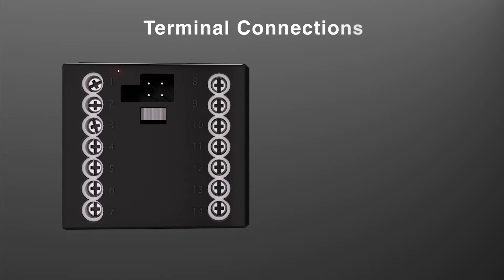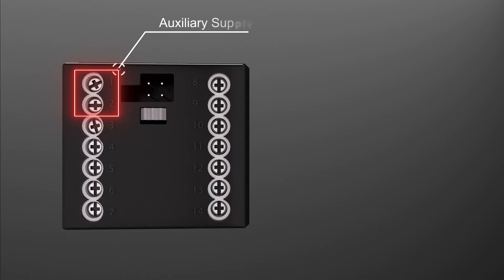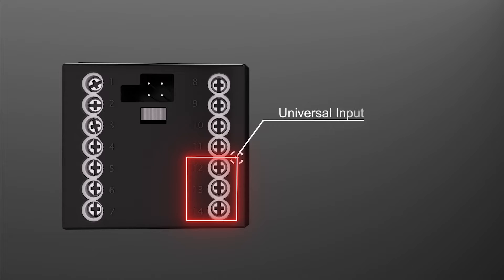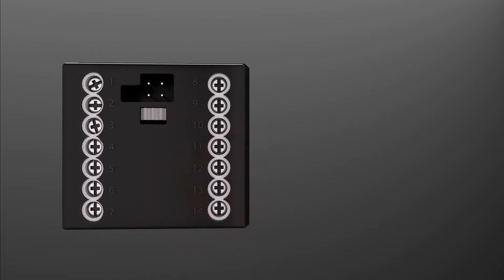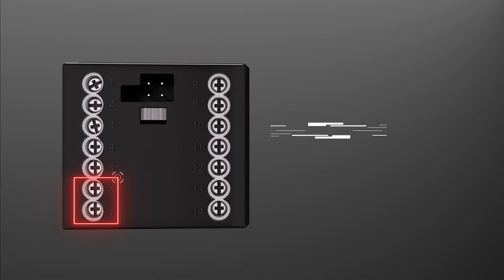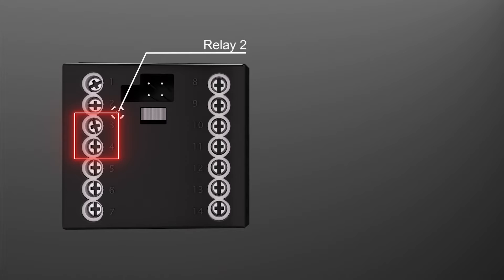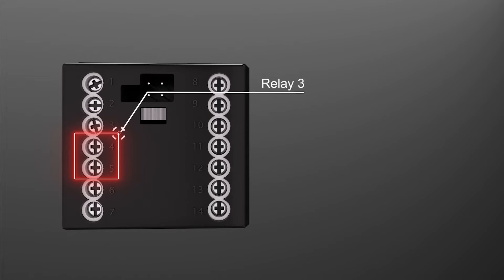Terminal connections: Terminals 1 and 2 for supply voltage. Terminals 14, 13, and 12 for RTD, thermocouple, milliampere, and voltage input. Terminals 10 and 11 for RS-485 Modbus communication. Terminals 8 and 9 for analog current, voltage, or SSR output. Terminals 6 and 7 for relay 1 output. Terminals 3 and 4 for relay 2 output. Terminals 4 and 5 for relay 3 output.